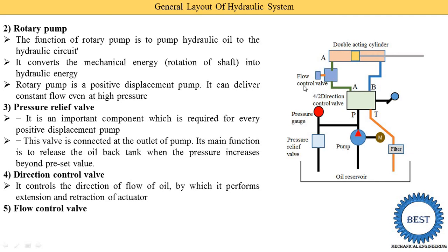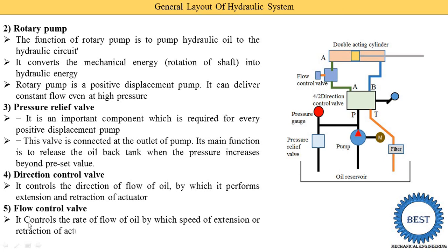The next component is the flow control valve. From its name, we understand it controls the flow — it controls the quantity of oil supplied to the cylinder. Sometimes the oil supplied to the cylinder is required at 2 liters per minute, sometimes 2.5 liters, sometimes 3, 4, or 5 liters. This is controlled by using the flow control valve depending on the pressure or force required. It controls the rate of flow of oil, by which the speed of extension or retraction of the actuator is controlled.